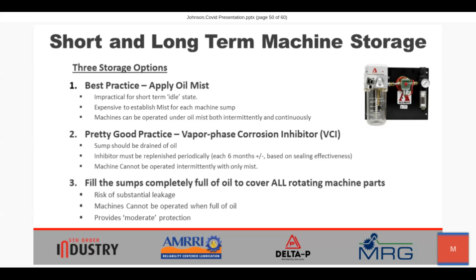We could turn them over very slowly by hand or with a shaft rotation device. And that would be acceptable, but we couldn't punch the start button and let it run for a couple of minutes if it's full of oil. Then lastly, this provides moderate protection. If we're going to do this, we should use rust and oxidation inhibited or turbine type of oil to take that approach.